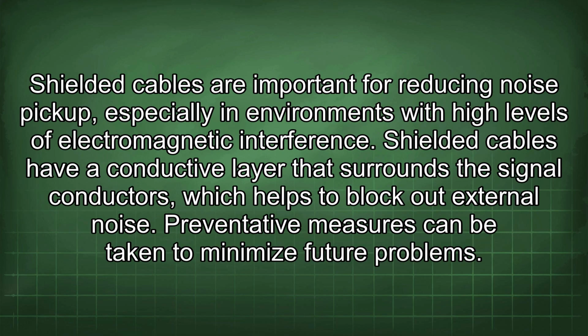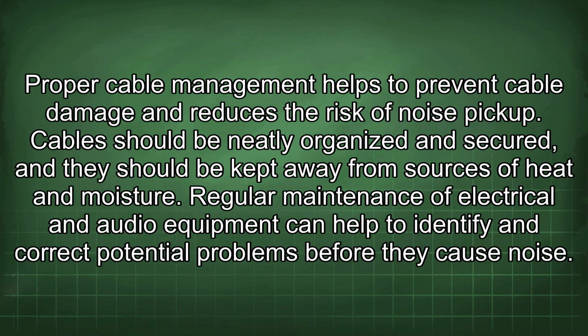Shielded cables are important for reducing noise pickup, especially in environments with high levels of electromagnetic interference. Shielded cables have a conductive layer that surrounds the signal conductors, which helps to block out external noise. Preventative measures can be taken to minimize future problems. Proper cable management helps to prevent cable damage and reduces the risk of noise pickup.